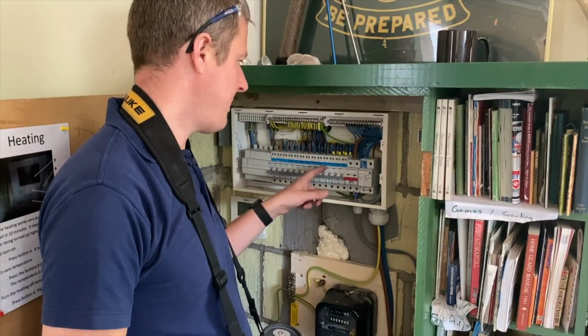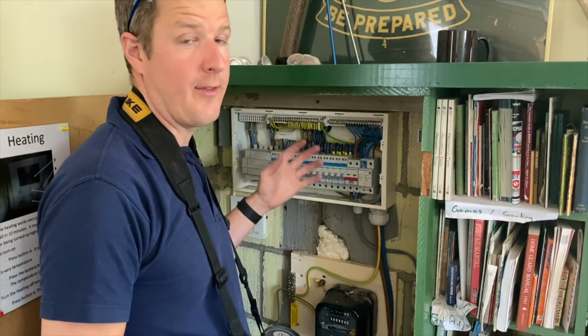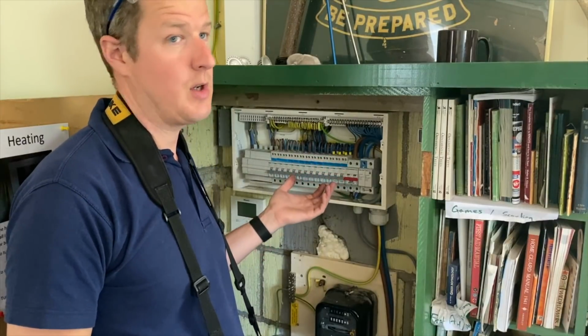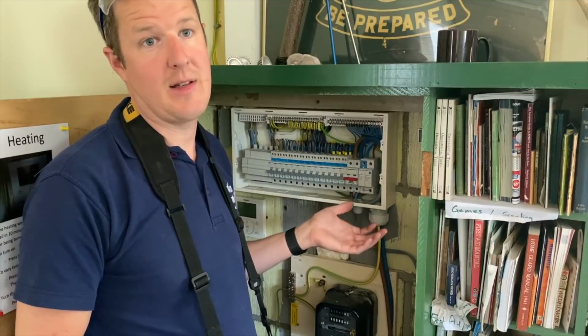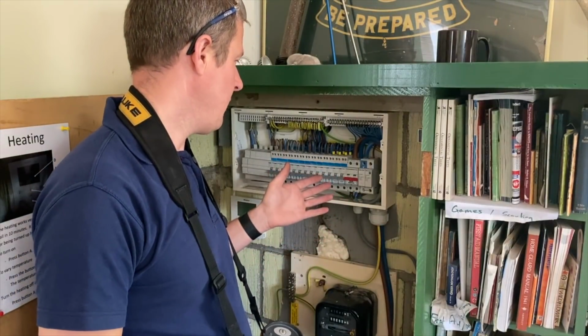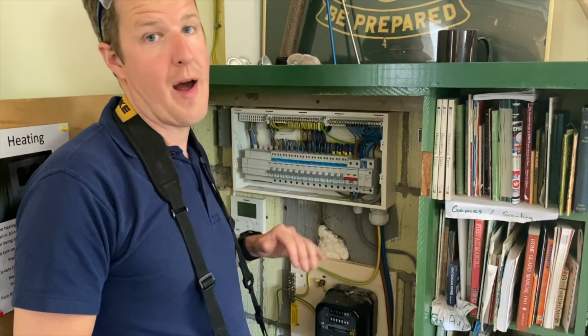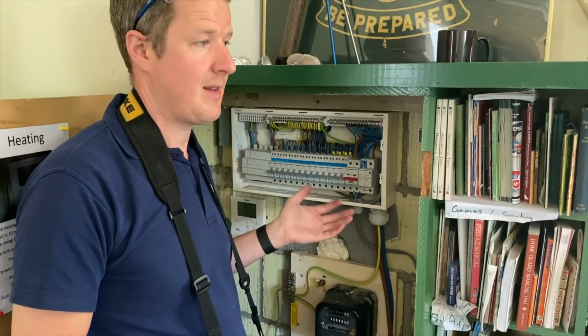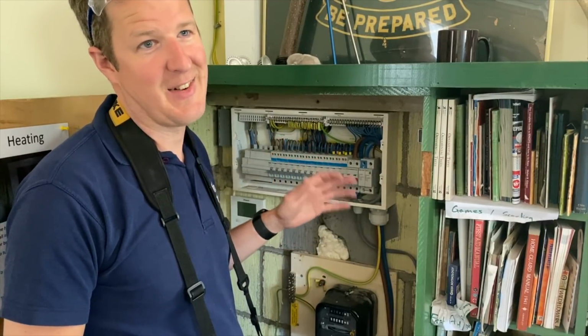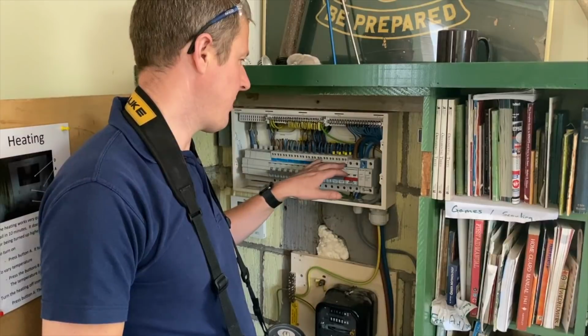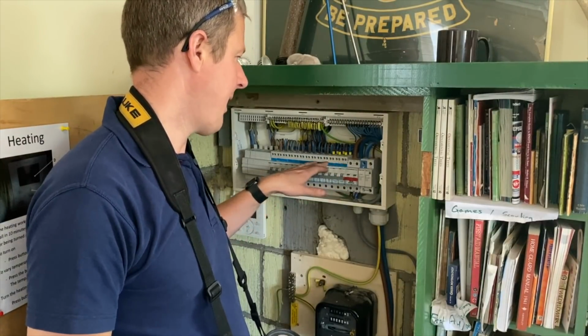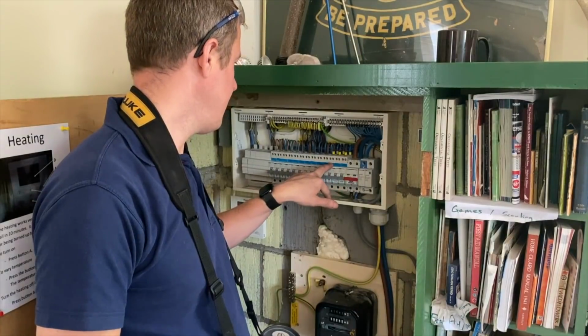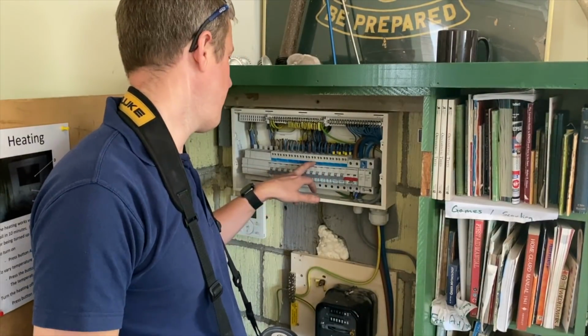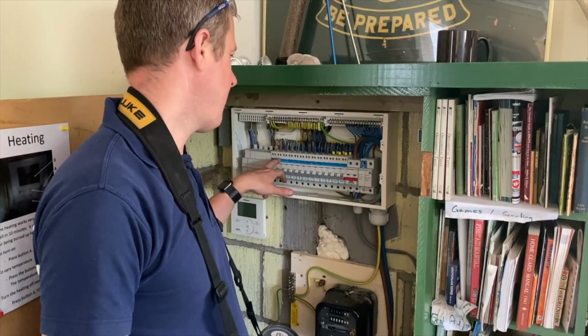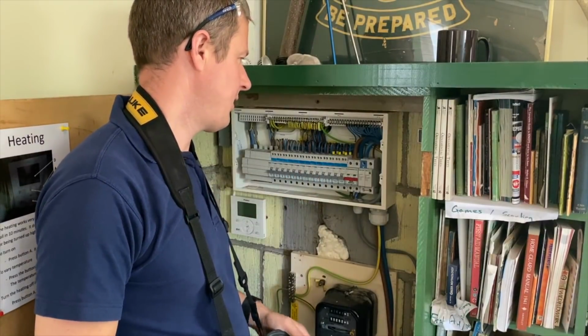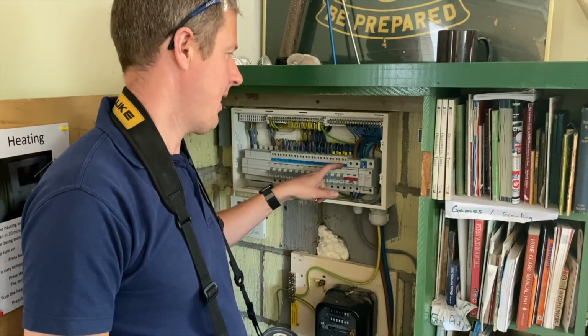Now, in the case of some installations where there's a lot of connected equipment, you will get false readings doing insulation resistance testing between live and neutral, and there's a possibility of damaging sensitive electronic equipment. So normally we put that as a limitation, or we go around and we disconnect every single light fitting, every single piece of sensitive equipment, but in reality that's very difficult to do. So some circuits we will do because we can test without risking damaging anything, like for example the cooker circuit will be fine. The socket circuits, if we unplug everything, then they'll be fine to do live to neutral. But the lighting, for example, and the fire alarm system, we won't do those tests live to neutral, we'll just do live to CPC and neutral to CPC.